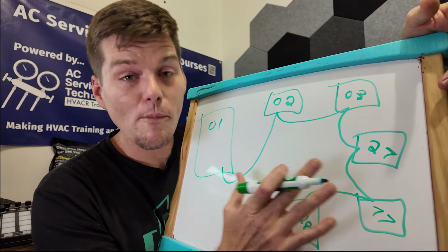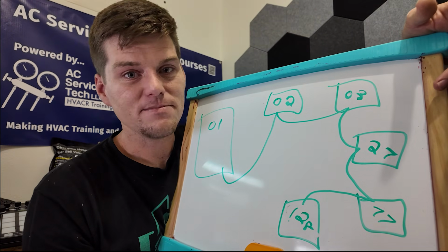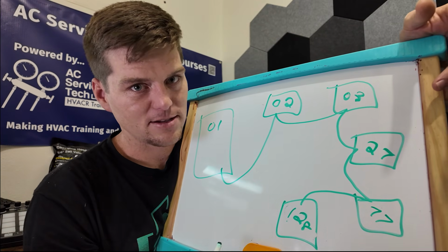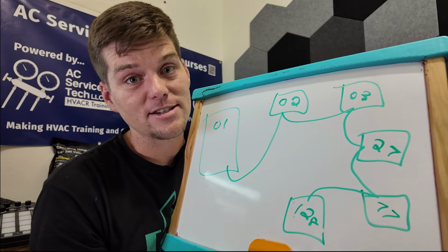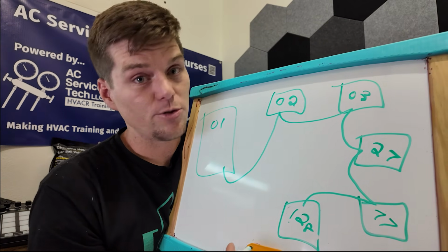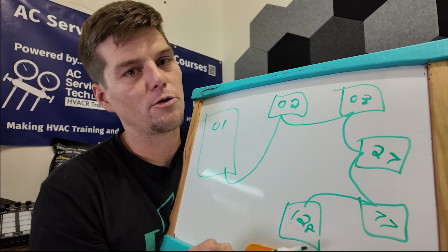And if it sees nobody, it's going to come back with a big old 0 of how many indoor units it sees. And so that's not a correct troubleshooting procedure for something like this. Looking at how many indoor units are connected is a snapshot of what it once saw, which is a good thing if you're trying to determine how many indoor units are connected to a mystery system. But it's not a good thing if you're trying to use that to prove communication.